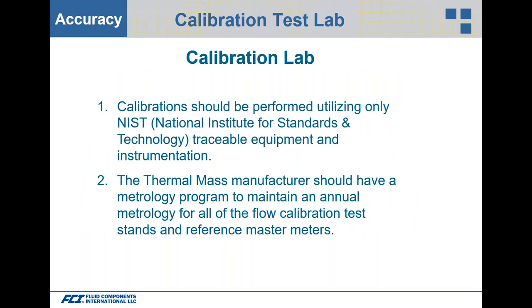Calibration test labs: calibrations should be performed utilizing only NIST — National Institute for Standards and Technology — traceable equipment and instrumentation. They should also maintain a metrology program, meaning annual service and verification on their primary meters. For example, FCI uses a turbine meter to calibrate thermal mass flow meters; every year that master meter is sent back to a NIST-approved agency for verification and recalibration.